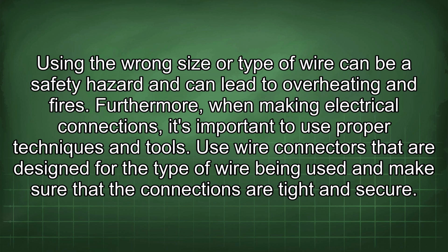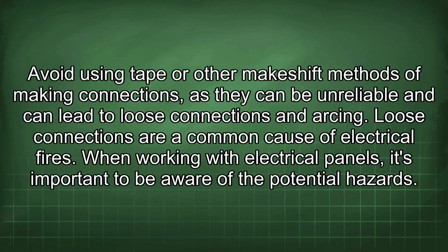Furthermore, when making electrical connections, it's important to use proper techniques and tools. Use wire connectors that are designed for the type of wire being used to make sure that the connections are tight and secure. Avoid using tape or other makeshift methods of making connections, as they can be unreliable and can lead to loose connections and arcing. Loose connections are a common cause of electrical fires.